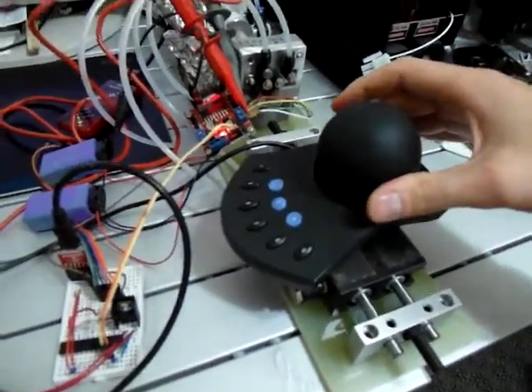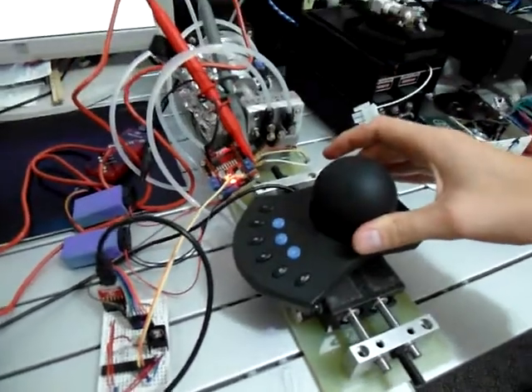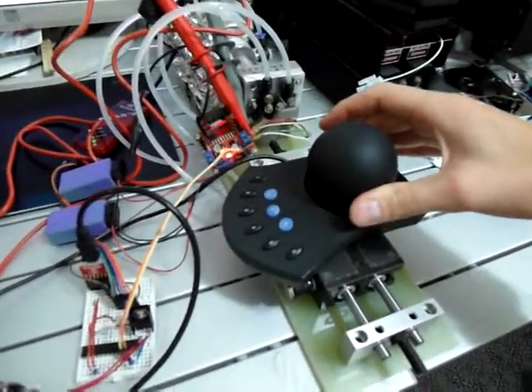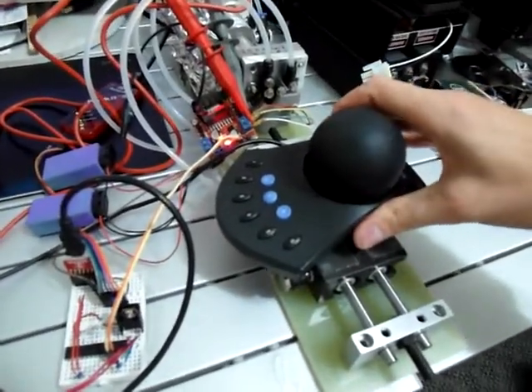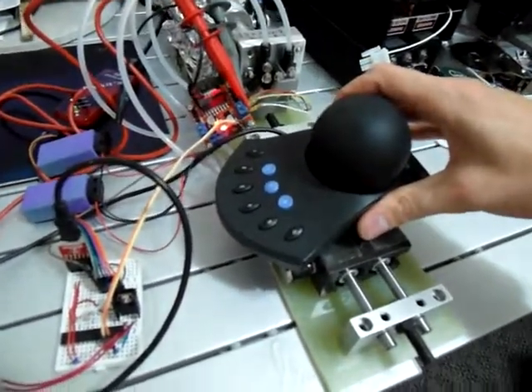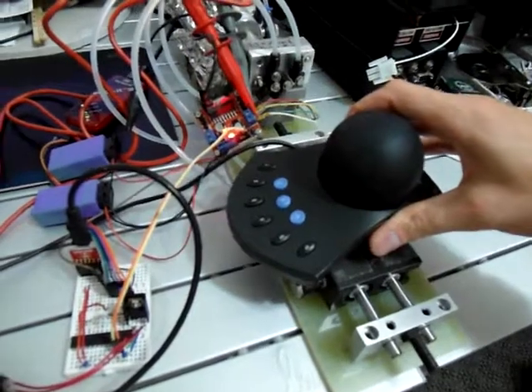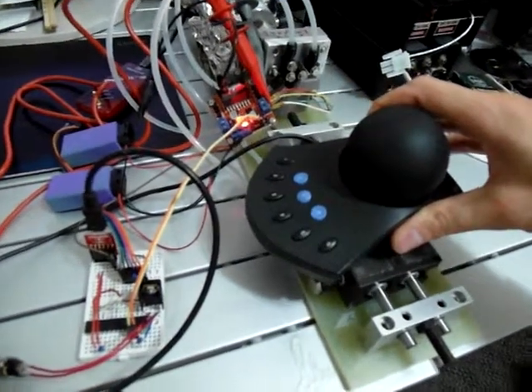Right now the servo valve is operating with around 100 psi differential pressure across the valve which is significantly less than its rated operation.